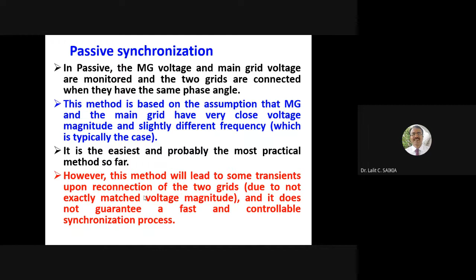This method is based on the assumption that the microgrid and the main grid have a very close voltage magnitude and slightly different frequency, which is typically the case. It is the easiest and probably the most practical method so far. However, this method will lead to some transients upon the reconnection of the two grids due to not exactly matching voltage magnitude, and it does not guarantee a fast and controllable synchronization process.